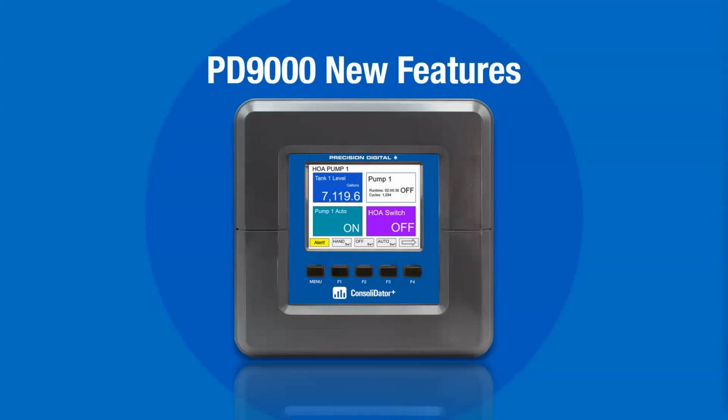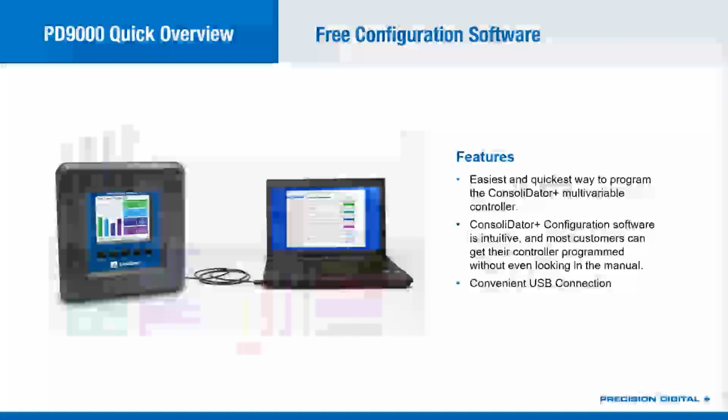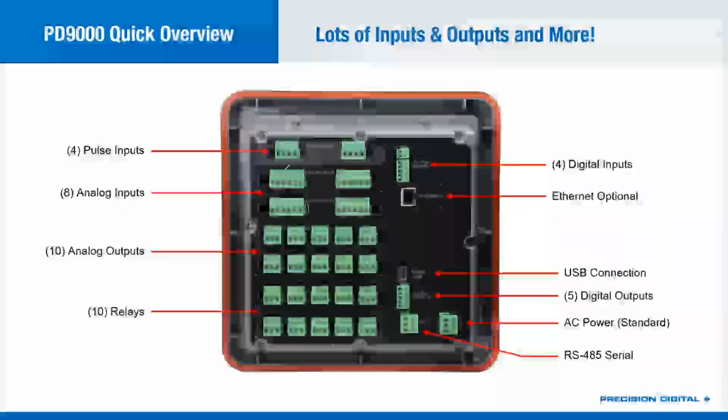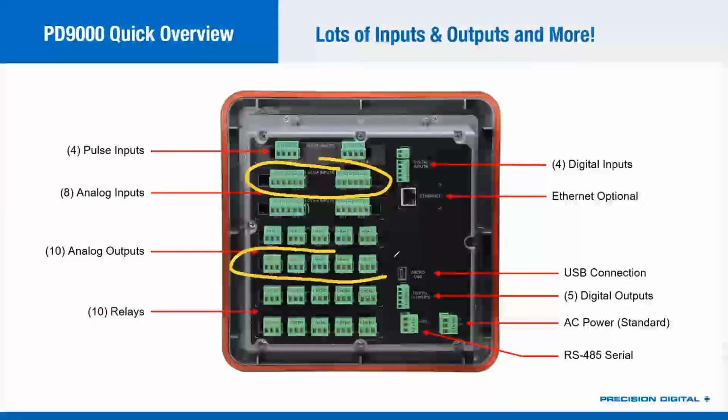And then Jonathan is asking, to sort of paraphrase your question here, there are power supplies that come with every 4 to 20 milliamp output and every 4 to 20 milliamp input. So all of your analog input cards and all of your analog output cards all have a power supply for each channel. So for example, the 5 analog outputs give me 5 isolated power supplies. And he's asking, how much current can I get out of the power supply?